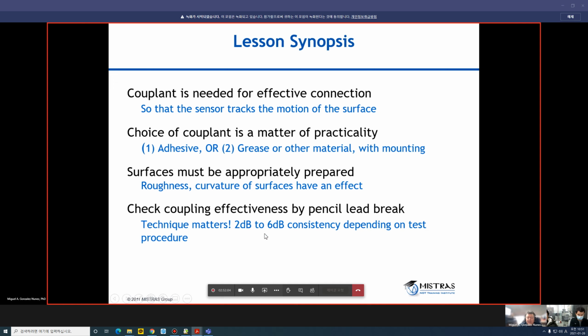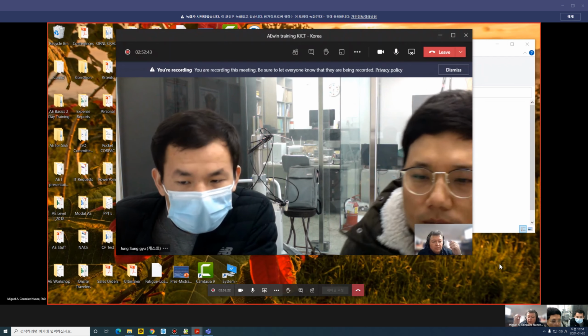I hope you have one of these. Yeah, we have it. Yeah, 0.2 millimeter 2H hardness. Yeah. Actually, 0.5. This is 0.3. Oh, okay. All right. So that's what we use to check the coupling of the sensors.